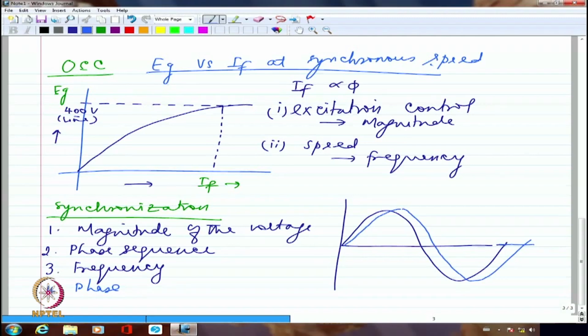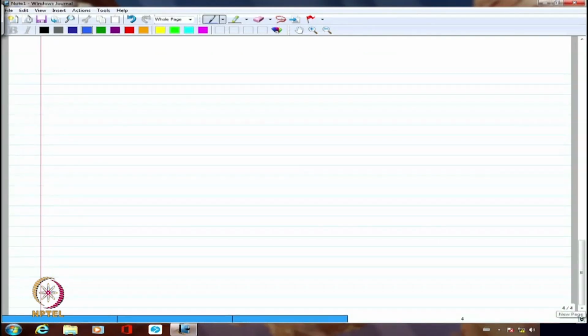So this process generally is automated in most of the power stations, where I have to synchronize the generator to the grid. That is automated because you are talking about hundreds of megawatt. So you don't want to do it manually and commit a blunder and have the whole thing blown over on the top of you. But what we do in the laboratory generally is done manually. So let us take a look at the synchronization process, how it is done for smaller generators.